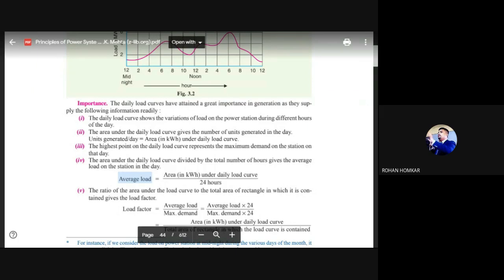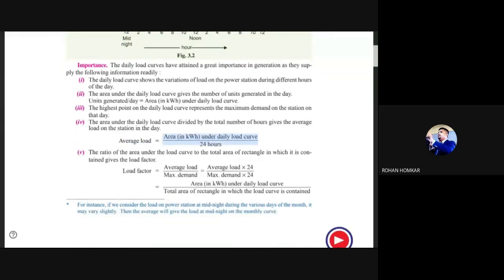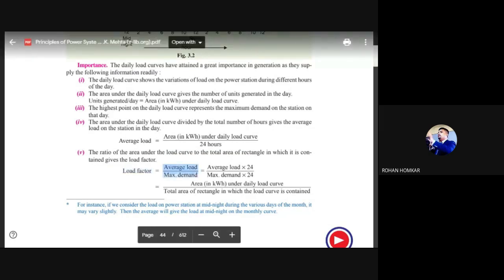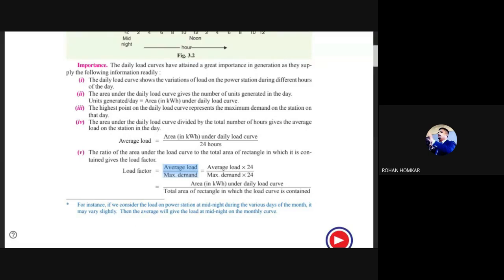To find average load, take total kilowatt-hours consumed in a day and divide by 24 hours. That gives the average load value. Load factor is average load divided by maximum demand. By this you can understand what percentage of the power plant's capacity is being utilized. If maximum demand is high and average load is low, the load factor will be low and efficiency will be poor.